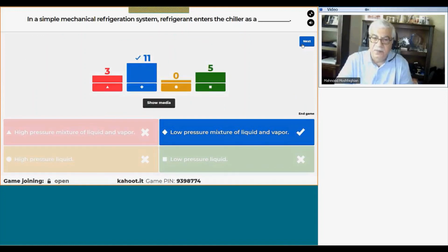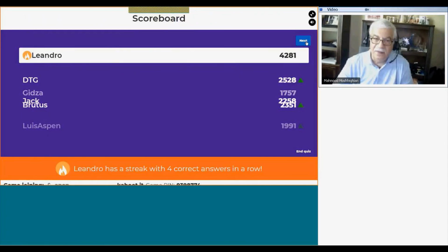Very good. Again, majority got it right. So we enter the chiller at low pressure. Condenser is the highest; discharge of the compressor is the highest pressure. Chiller has the lowest pressure. And if one day we can get into a chiller 100% liquid, I think we would become millionaires. Excellent, Leandro.